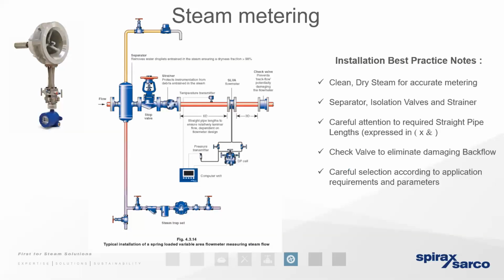And we also know that when we're looking at steam meters, we need to observe good working practice to ensure that the steam meter is fitted correctly. It's not a single item. It needs to be fitted in conjunction with the conditioning ancillaries. For example, we've got the separator here and we've got the strainer. The strainer and the separator protect the flow meter from any debris or effects of erosion. And an excess of moisture present in the steam means that the steam isn't going to have the mass flow rate that was expected.